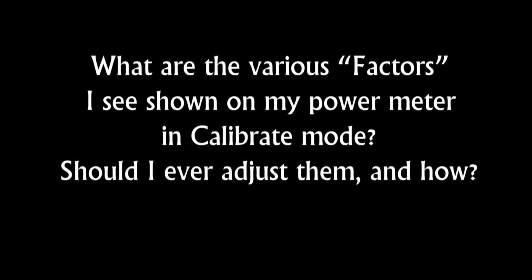What are the various factors shown on a power meter in calibrate mode, and should you ever adjust them? There are a number of different factors in calibration mode, each with a different role. Some are user adjustable, for example when you need to calibrate against your own in-house master reference. Adjusting any internal calibration factor voids the factory calibration. This should only be done in a case of clear need, only with the greatest of care, and only by properly qualified personnel. If you're not sure whether you really need to adjust these factors, you probably should not be doing it.